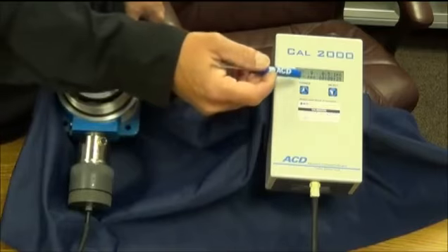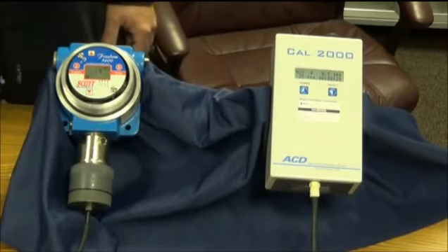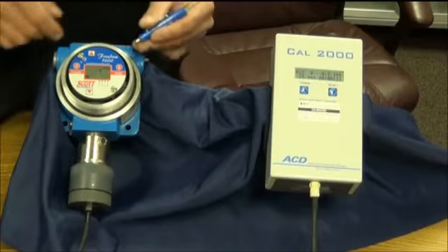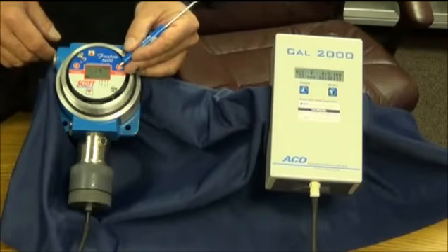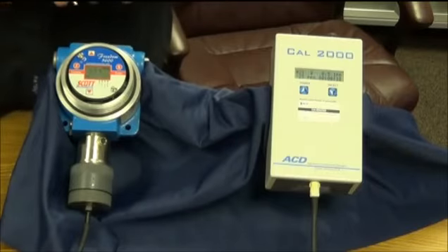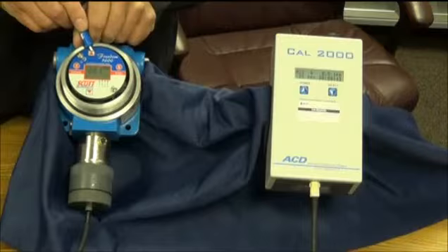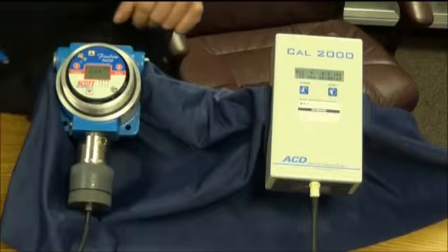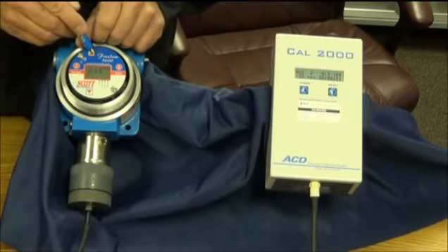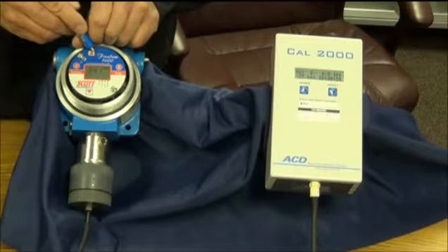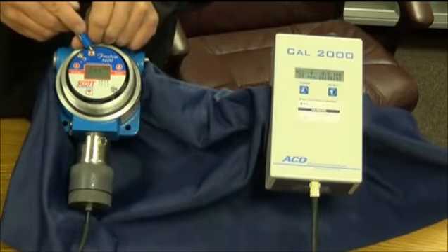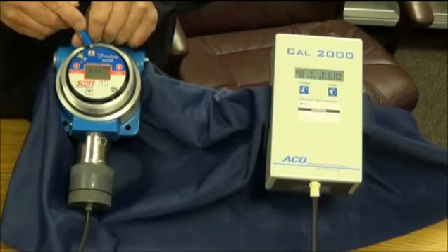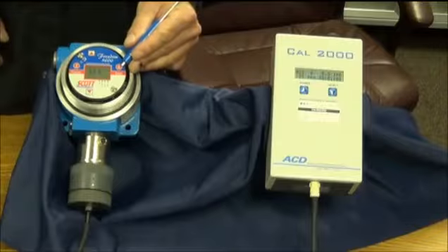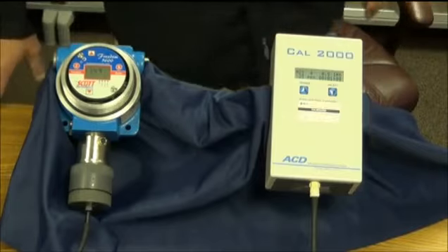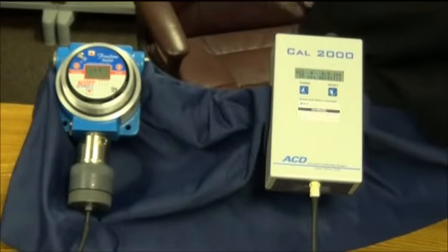Alright, now the Cal 2000 is stabilized at 25 parts per million, and we're going to span this Scott sensor up to read 25. Again, it's done with a magnetic screwdriver. We hold it over the span, and then there's the up and down arrows. I'm going to bring this up to 25 parts per million. Alright, there's 25. We hit set. It shows you its calibration number there, and then it's going to read 25 ppm.